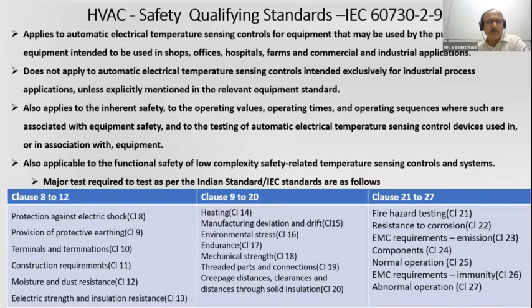What are the different kinds of checks as per the standards: protection related to shock, protection related to proper earthing, terminal properly connected, construction, moisture related resistance, electrical strength, heating related performance like endurance testing, environmental stress testing, mechanical strength, as well as creepage related to distance between the PCBs and critical components, and fire hazard related testing, resistance to corrosion like salt spray test and all these things.